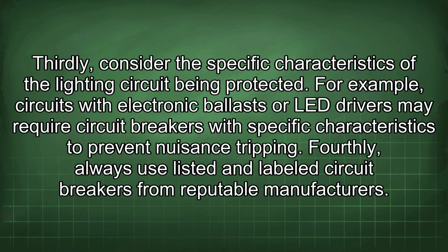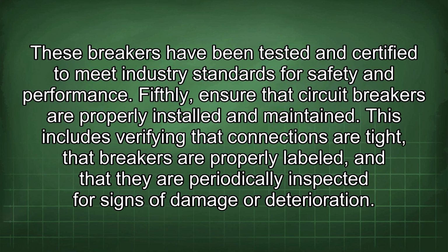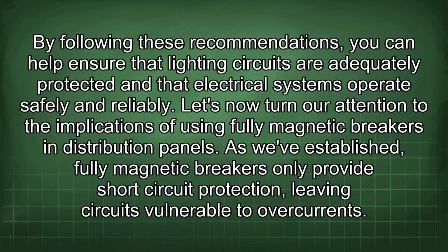Thirdly, consider the specific characteristics of the lighting circuit being protected. For example, circuits with electronic ballast or LED drivers may require circuit breakers with specific characteristics to prevent nuisance tripping. Fourthly, always use listed and labeled circuit breakers from reputable manufacturers. These breakers have been tested and certified to meet industry standards for safety and performance. Fifthly, ensure that circuit breakers are properly installed and maintained. This includes verifying that connections are tight, that breakers are properly labeled, and that they are periodically inspected for signs of damage or deterioration. By following these recommendations, you can help ensure that lighting circuits are adequately protected and that electrical systems operate safely and reliably.